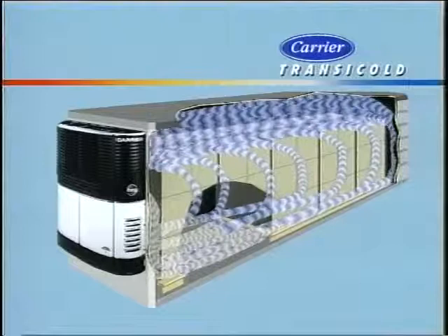The Ultima 53 with the advanced microprocessor system is designed to start itself automatically under normal conditions, although in cold ambients it may be necessary to start the unit manually, since a longer glow time may be required. The manual glow crank switch has been moved to the rear of the electrical box on the Ultima and on the side of the control box, accessible through the front roadside door, on the Ultra, Ultra XL, and Extra. The switch is now easily reached from beneath the unit.